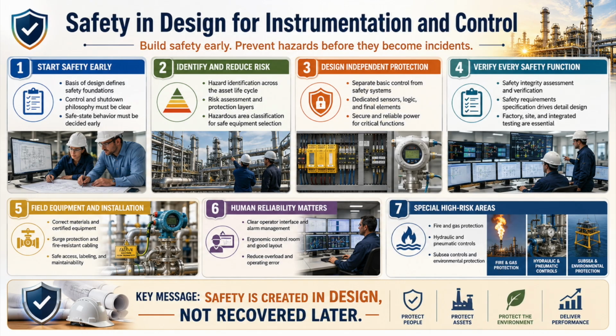Your first safeguard is not a shutdown system. Your first safeguard is a sound basis of design. The basis of design must establish governing requirements, site conditions, operating modes, automation philosophy, shutdown and isolation strategy, availability targets, secure power needs, abnormal operating requirements, future expansion, and the boundary between normal control and safeguarding. If these foundations are vague, every later document inherits uncertainty.